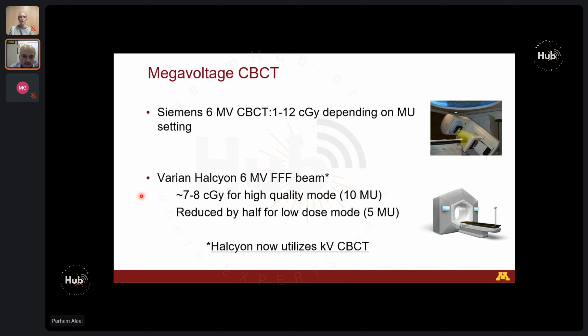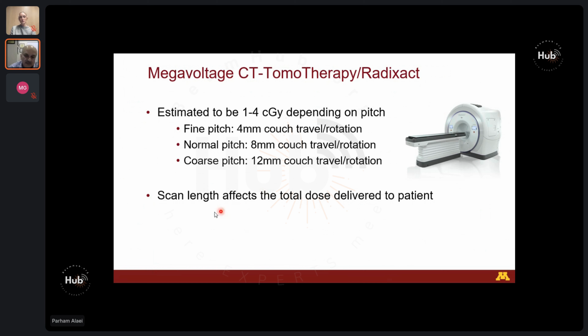And then for TomoTherapy Radixact, again, there are estimates on that. It depends on the pitch: fine pitch, more dose; coarse pitch, less dose. So if they're treating a patient with a long extremity or a spine field or craniospinal, the coarse pitch should be used because it's a lot less dose. But if you're treating a brain lesion, for example, then you have to use a fine one because you need the resolution for that. And the scan length affects the total dose delivered to the patient in the case of TomoTherapy.